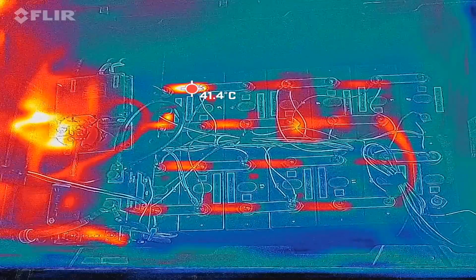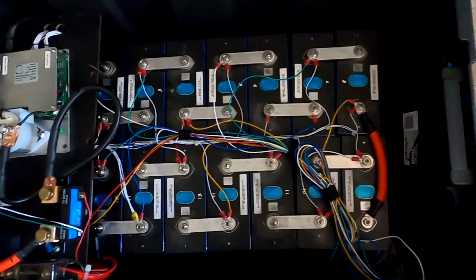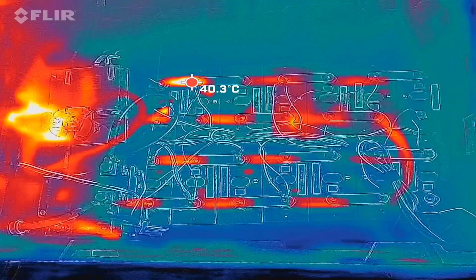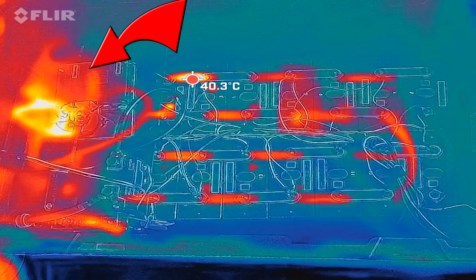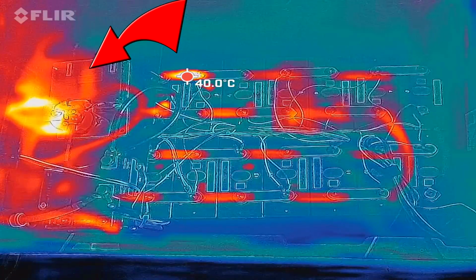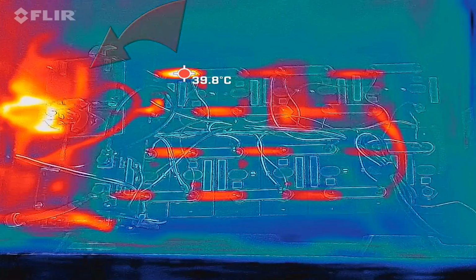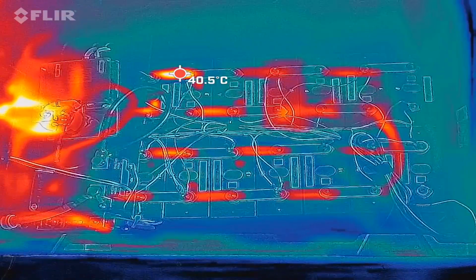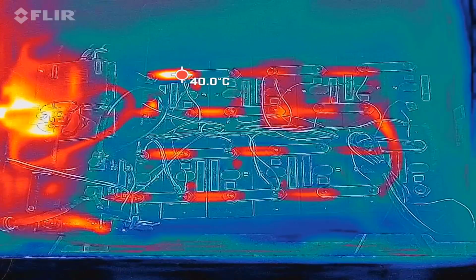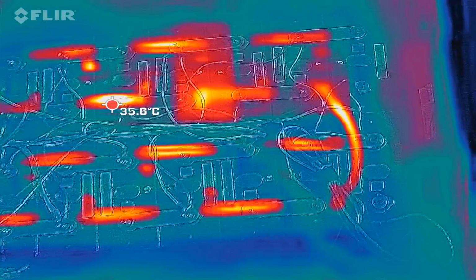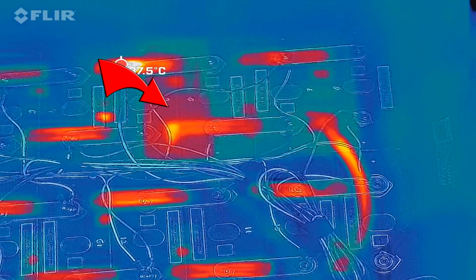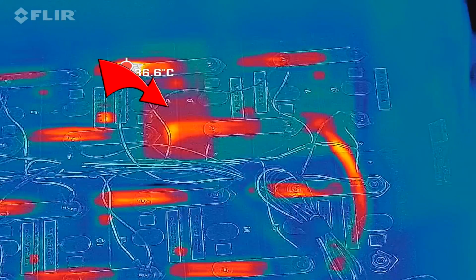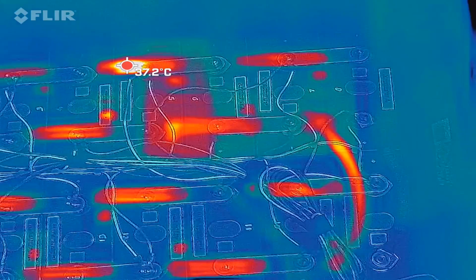We are now looking at our battery through the infrared camera. On the left is the BMS with its relay turned on, which is fairly hot. We can also see a bus bar at 40 degrees. But further down, cell number 6 has completely heated up on the positive terminal already, and this is with almost 30 amps now.